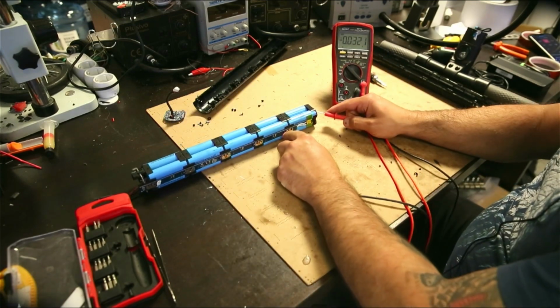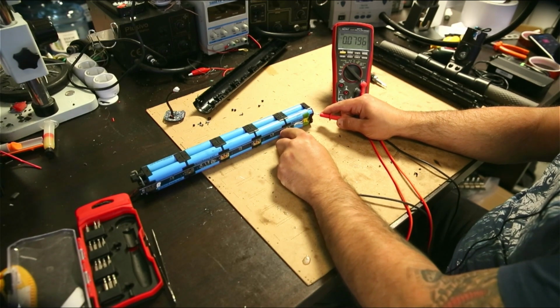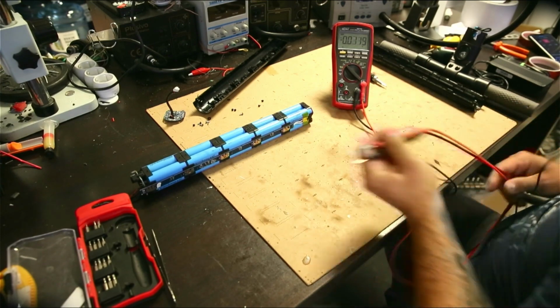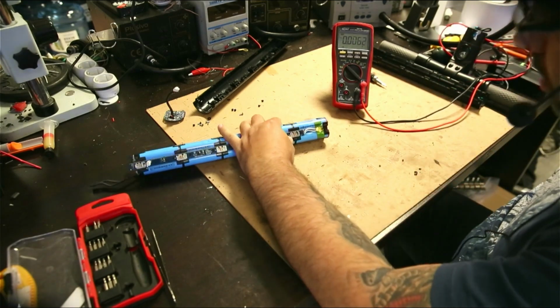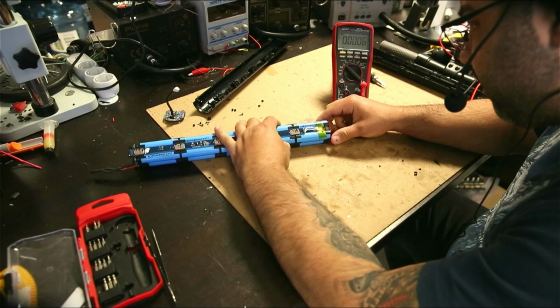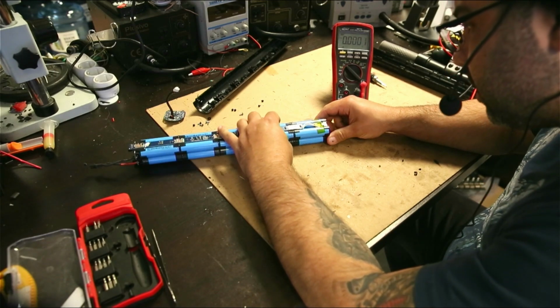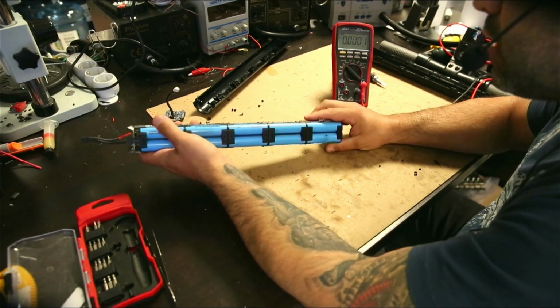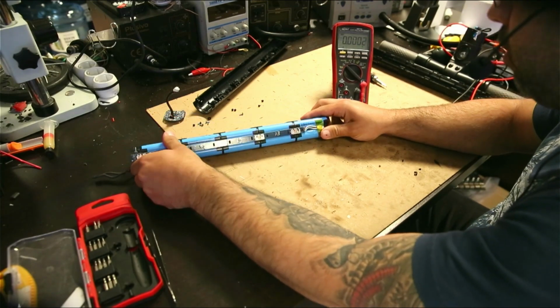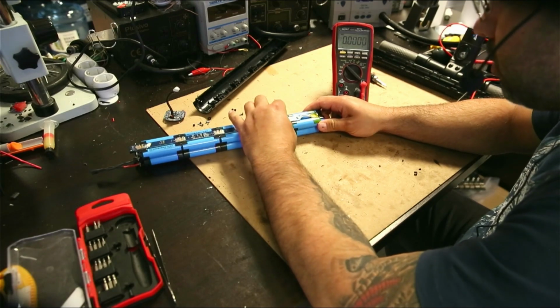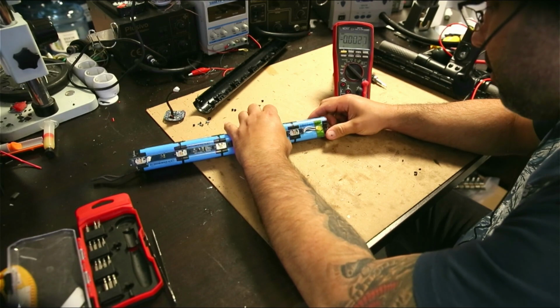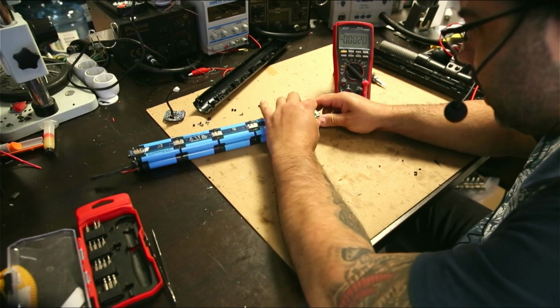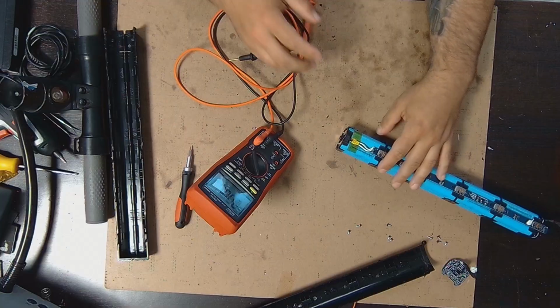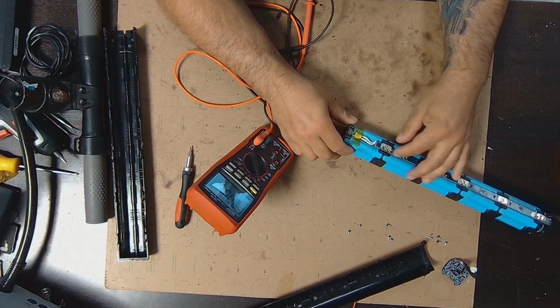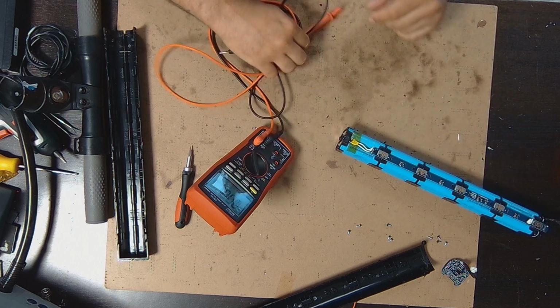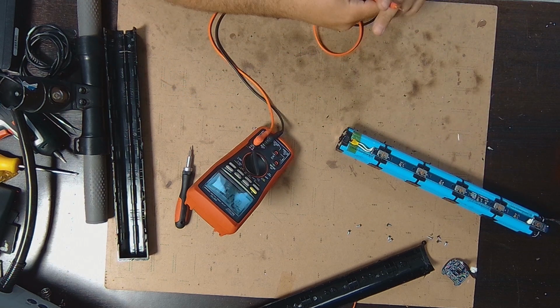So all the cells but this one are working fine, and that's like I said, usually it's a problem with the batteries, and it can be a problem with the BMSs also, because they are not using energy from all the packs, they use energy from one cell to keep them alive. I did not study this BMS too much, but I worked with others before and they had similar issue. So that's what most of the time happens with other packs as well. One of the cells will get disconnected or get discharged.